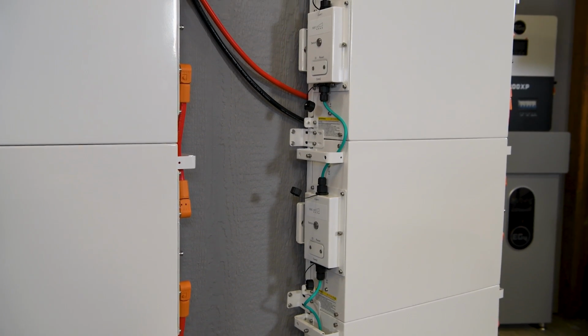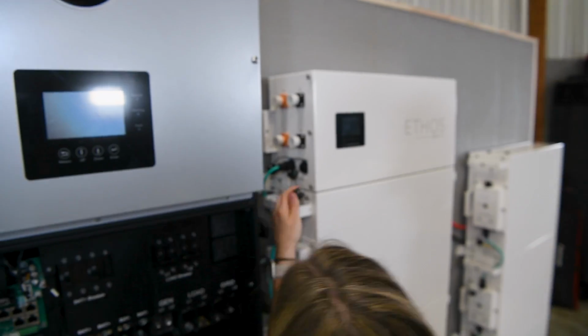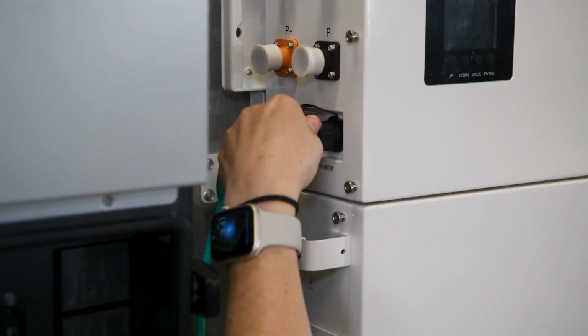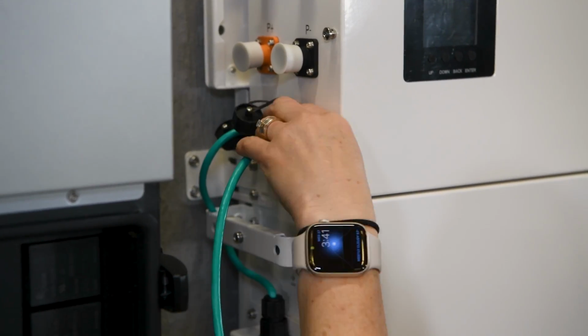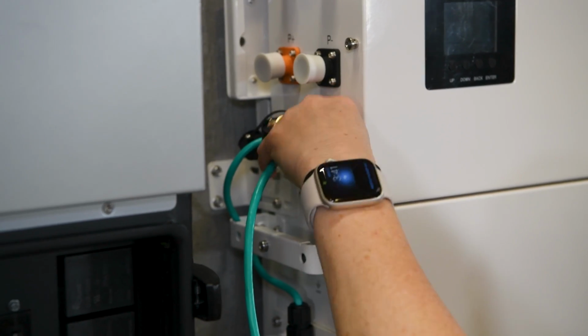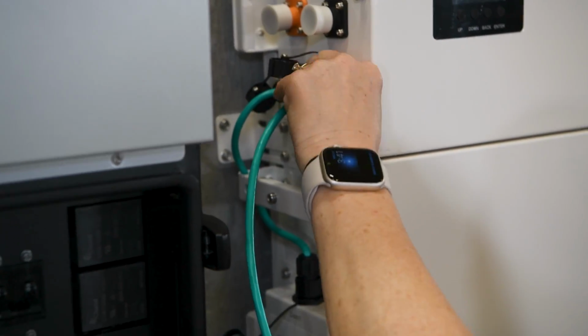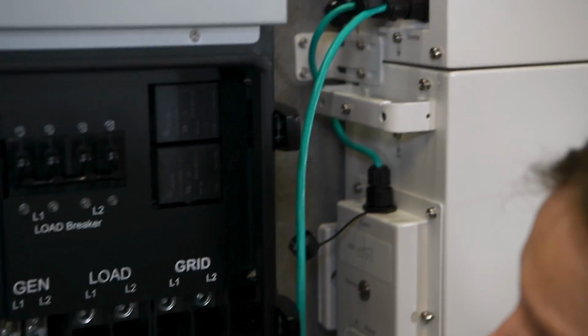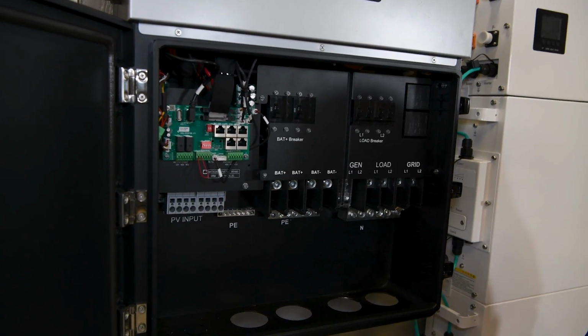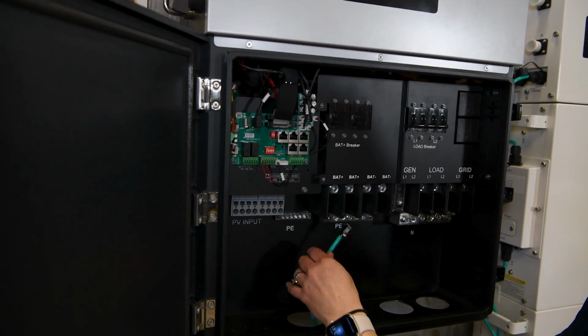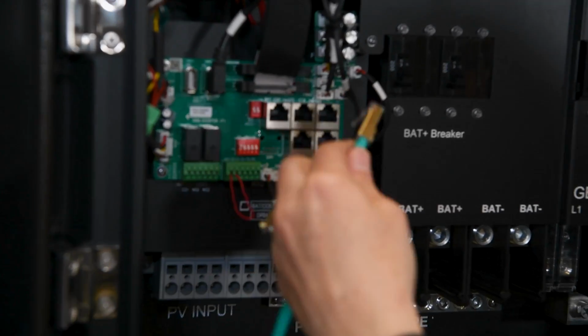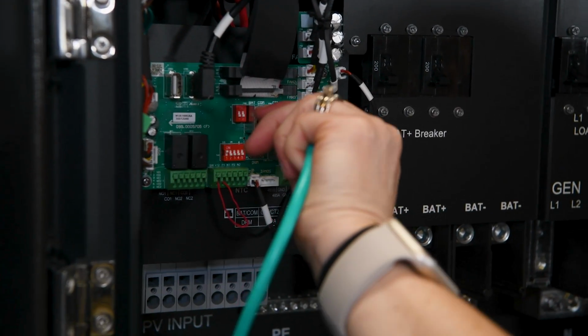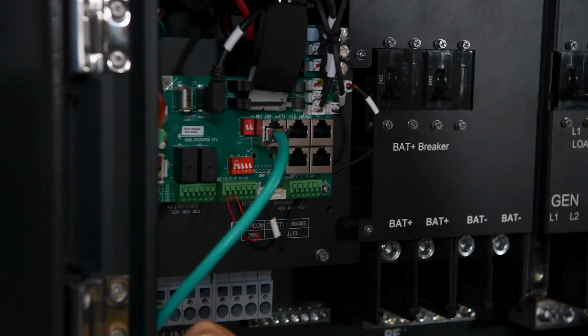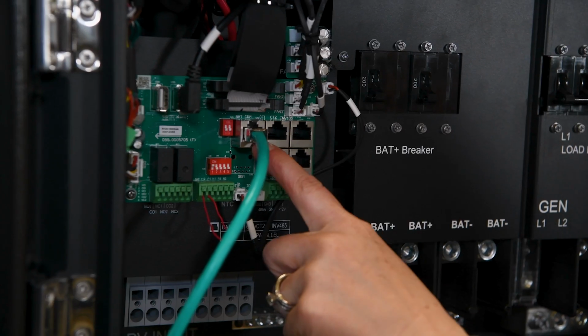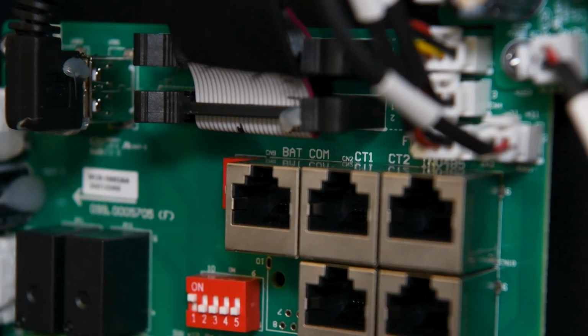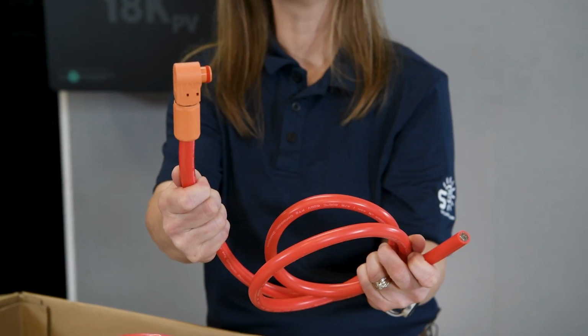Now it's time to link our controller box with the inverter. Grab the longer communication cable, which has a standard RJ45 connector on one end and a screw-in connector on the other. Attach the screw-in connector to the control box on the left side where it's marked inverter, tightening it until secure. Then take the RJ45 end and connect it to the inverter. For the EG4 18kPV, you'll find the appropriate communication port located at the top left corner of the board, clearly labeled battery communication.